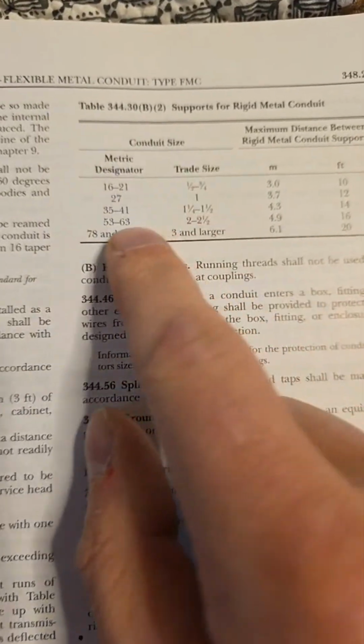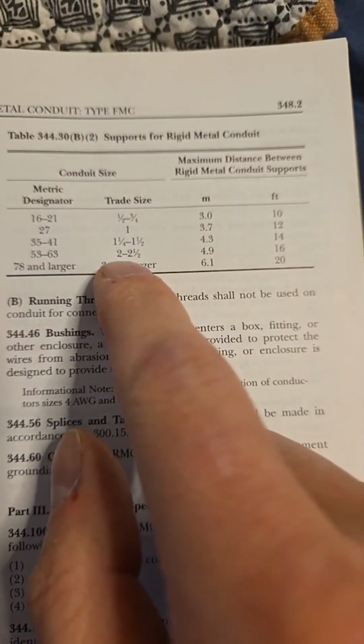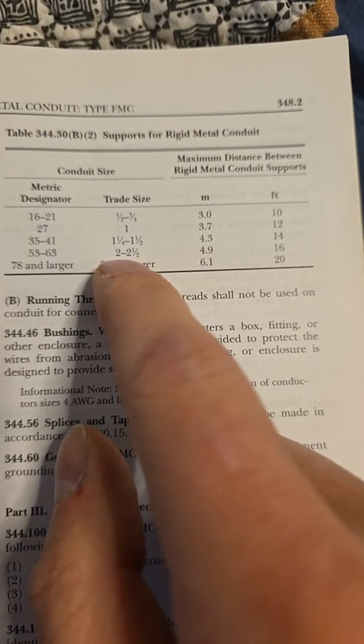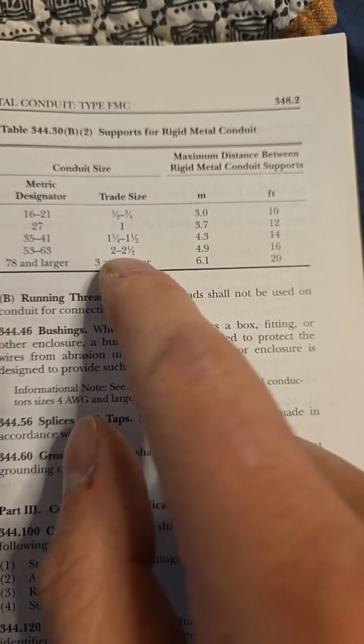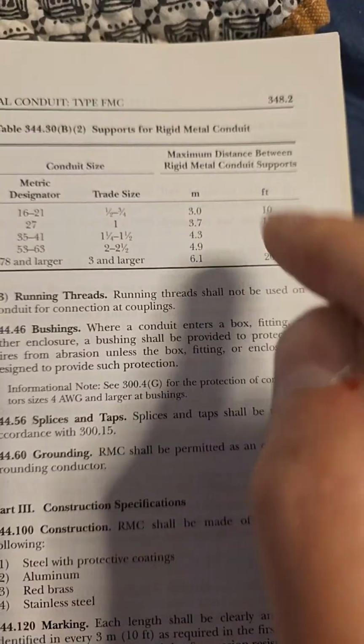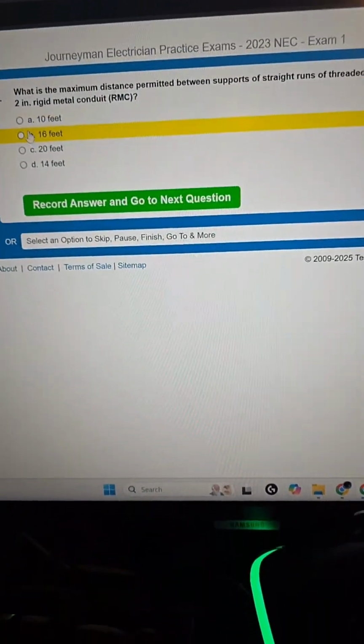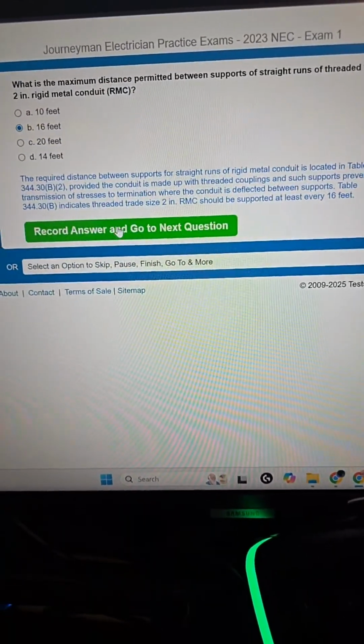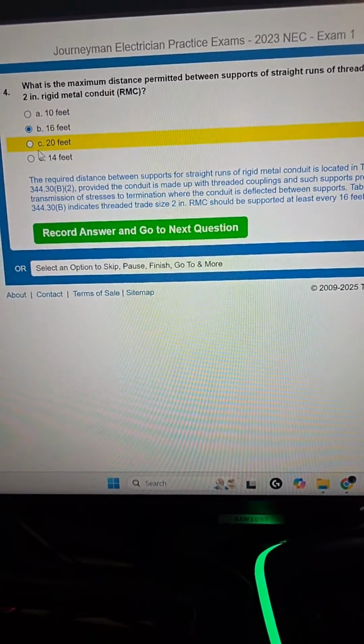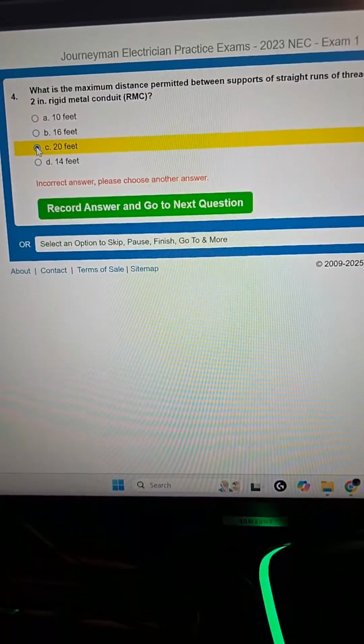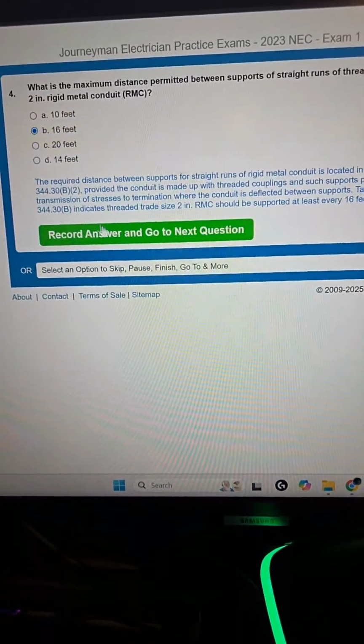So if we read this, it'll tell us to go back here to B2. See right here, B2, and then this is B2 up here. So we see here that we got 2-inch RMC, and we're looking at 16 feet. So we go over here, 16 feet should be the answer. And there it is there. If I click the wrong one, what happens? Good. Okay. So 16 feet it is.